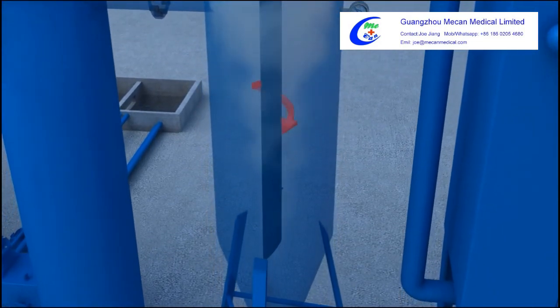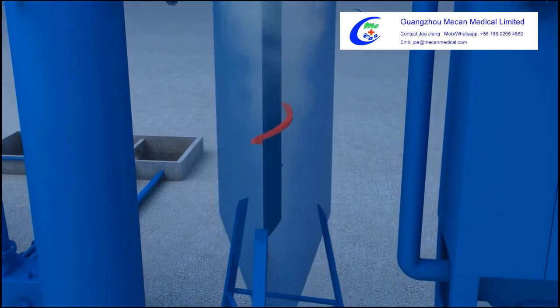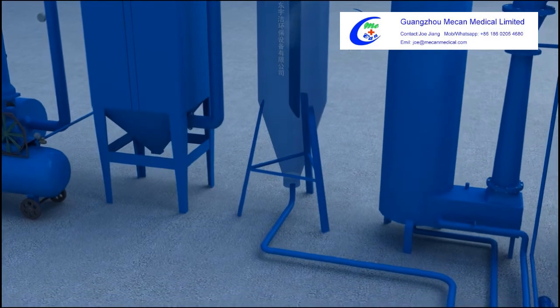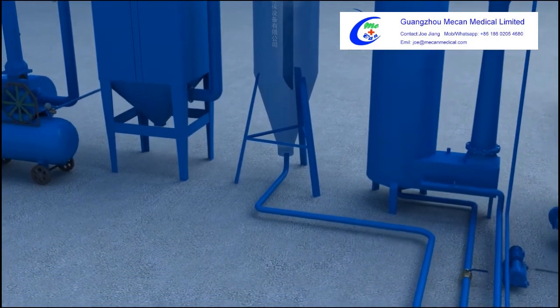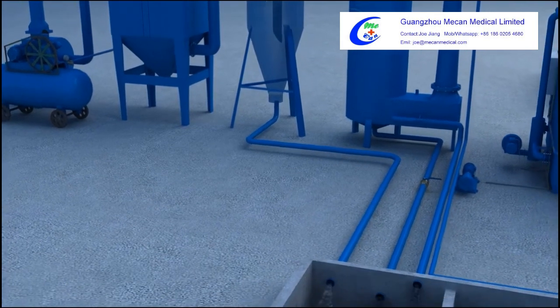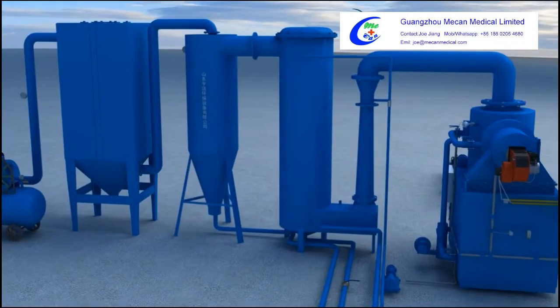Process 4: The low-temperature water-containing gas flows into the dust-water separator tangentially. Water contained in the gas is separated by means of centrifugal and conical force, with a dehydration rate of over 98%. The separated water flows back to the tank and is recycled.